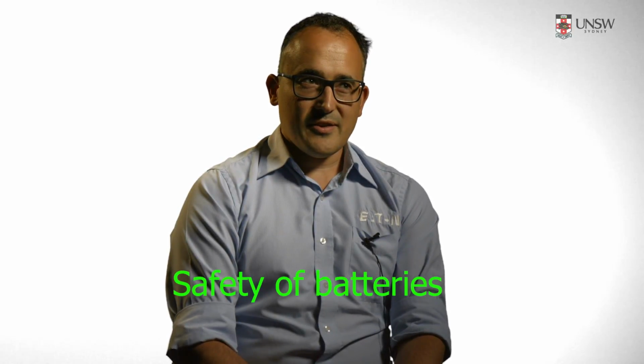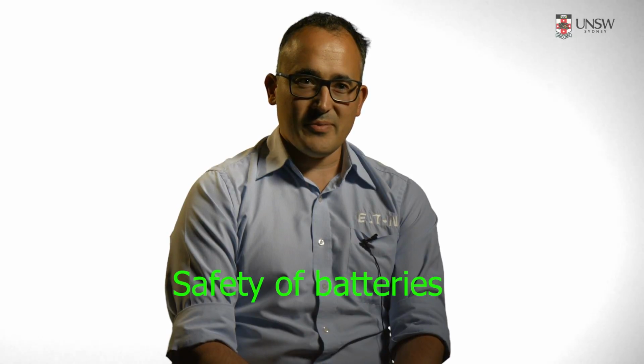Batteries represent a unique challenge in that a battery cannot be turned off. So once a battery has a charge, there's always a potential across the terminals, whether that potential is 12 volts, or in a large battery string you might have 480 volts, 500 volts, and so on. So within our risk controls, we cannot eliminate the risk that a battery presents simply by turning it off, because a battery cannot be isolated, it's always live. So that presents a unique challenge within our equipment.